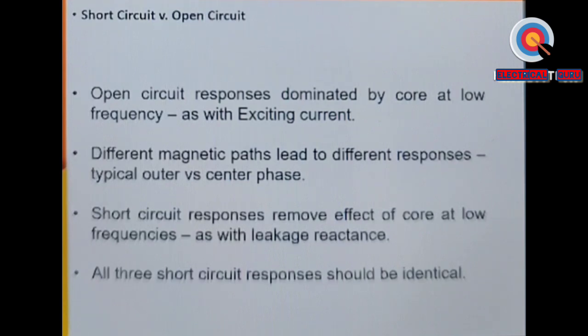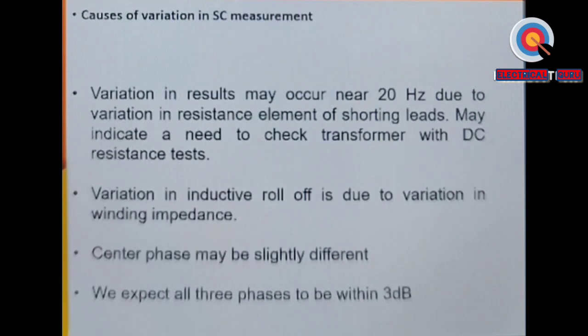Short circuit responses remove the effect of the core at low frequencies, as with leakage reactance. All three short circuit responses should be identical. Variation in the results may occur near 20 Hz due to variation in resistance elements of shorting leads, and may indicate a need to check the transformer with a DC resistance test. Variation in inductive roll-off is due to variation in the winding impedance. Central phase may be slightly different. We expect all three phases to be within 3 dB. So this is a typical plot.